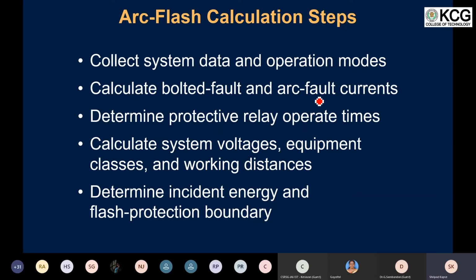So just to mention, there is a difference between the bolted fault current and the arc fault current. A bolted fault is where two conductors come in contact, in which case the fault resistance is basically zero. But as the temperature rises between these bolted conductors, slowly the solid conductor starts going into a molten state, and a gap is generated between the two conductors. Now there is an arc between these conductors, and for this arc the air is the resistance medium. The air offers some resistance, due to which there is a reduction in the arc fault current as well. IEEE 1584 also provides guidelines on how to calculate the arc fault current.